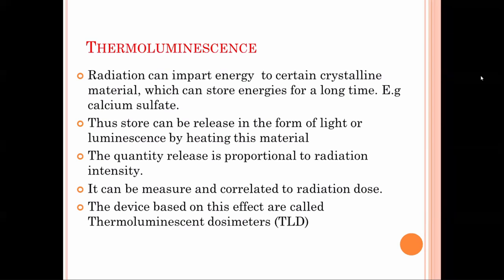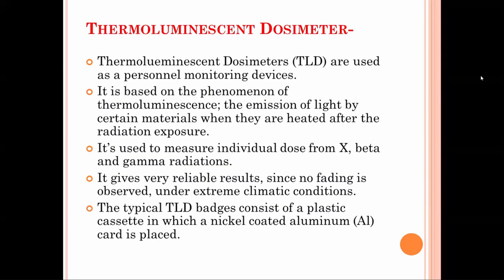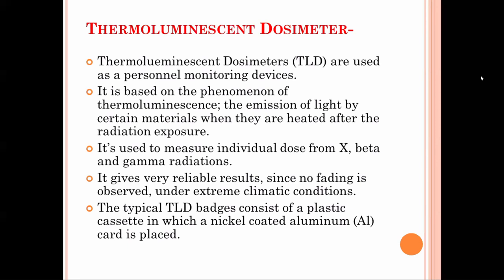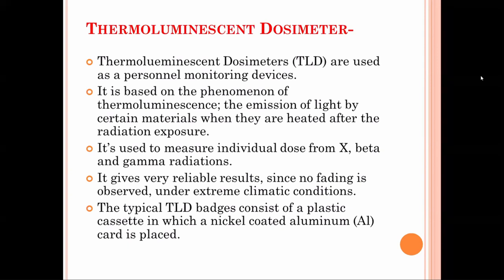The quantity of radiation is proportional to the radiation intensity, which can be measured and correlated to dose. A device based on the effect of thermoluminescence is called a thermoluminescence dosimeter. The TLD is used as a personal monitoring device and is based on the phenomenon of thermoluminescence — emission of light by certain material when heated. It is used to measure individual dose from X-ray, beta, and gamma radiation.